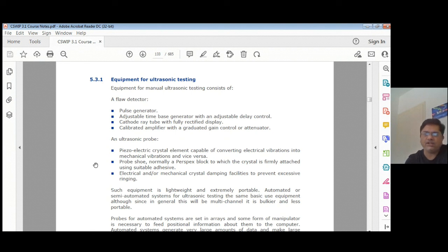So जैसा मैंने आपको बोला कि piezoelectric crystal element capable of converting electric vibration into mechanical vibration and vice versa. Mechanical vibration also, when you get back, should be able to convert into electrical vibration. Probe shoe normally perspex block like a plastic or silica, which the crystal is firmly attached, and then this is the probe. I'm showing the photograph of the probe. Then electrical and mechanical crystal damping facility to prevent excessive ringing. So what is this? Is that since a lot of signals will be generated, you need some kind of system to identify the good signal and bad signal.